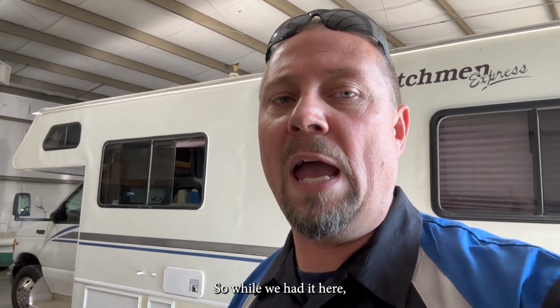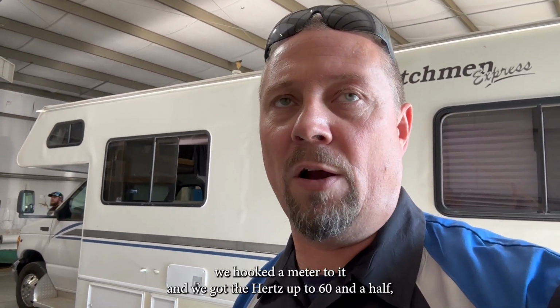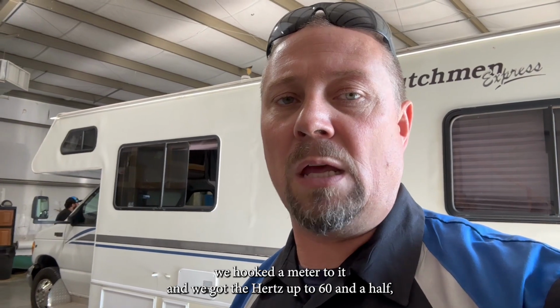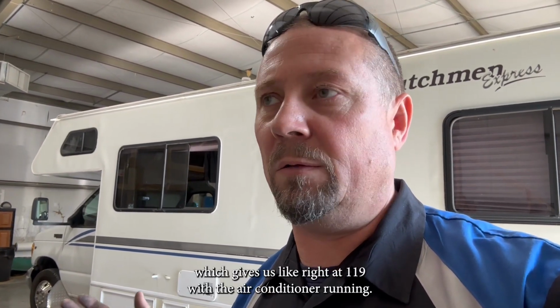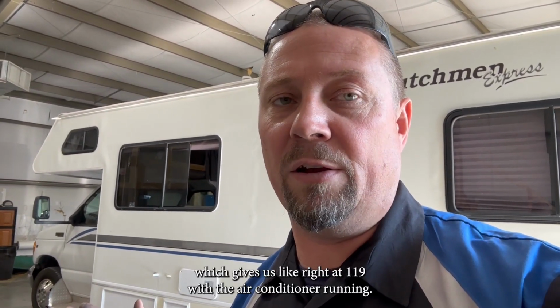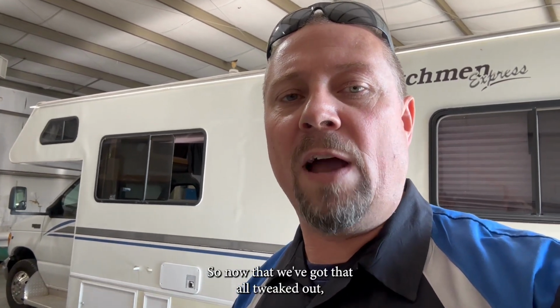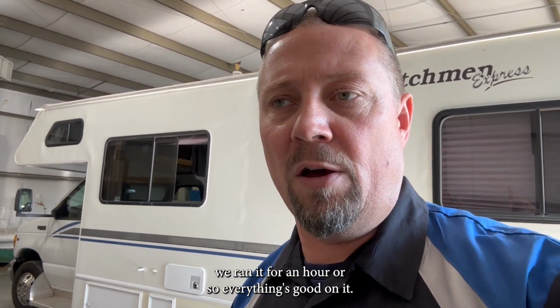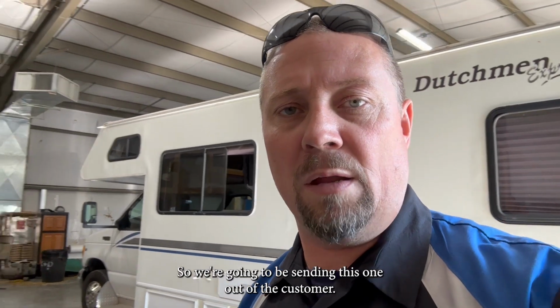So while we had it here, we hooked our meter to it and we got the hertz up to 60 and a half, which gives us right at 119 with the air conditioner running. So now that we've got that all tweaked out, we ran it for an hour or so, everything's good on it, so we're going to be sending this one out to the customer.